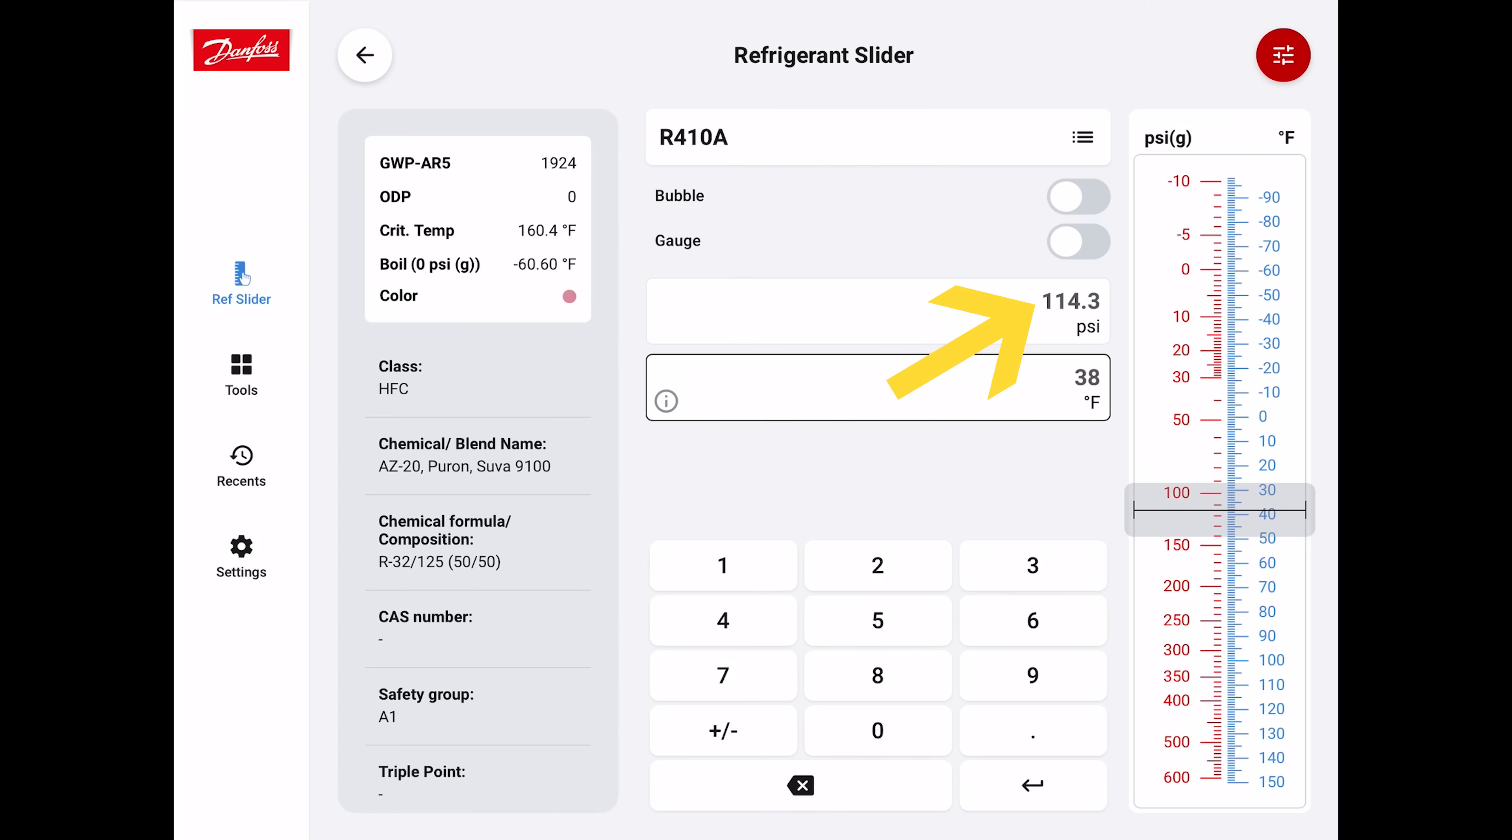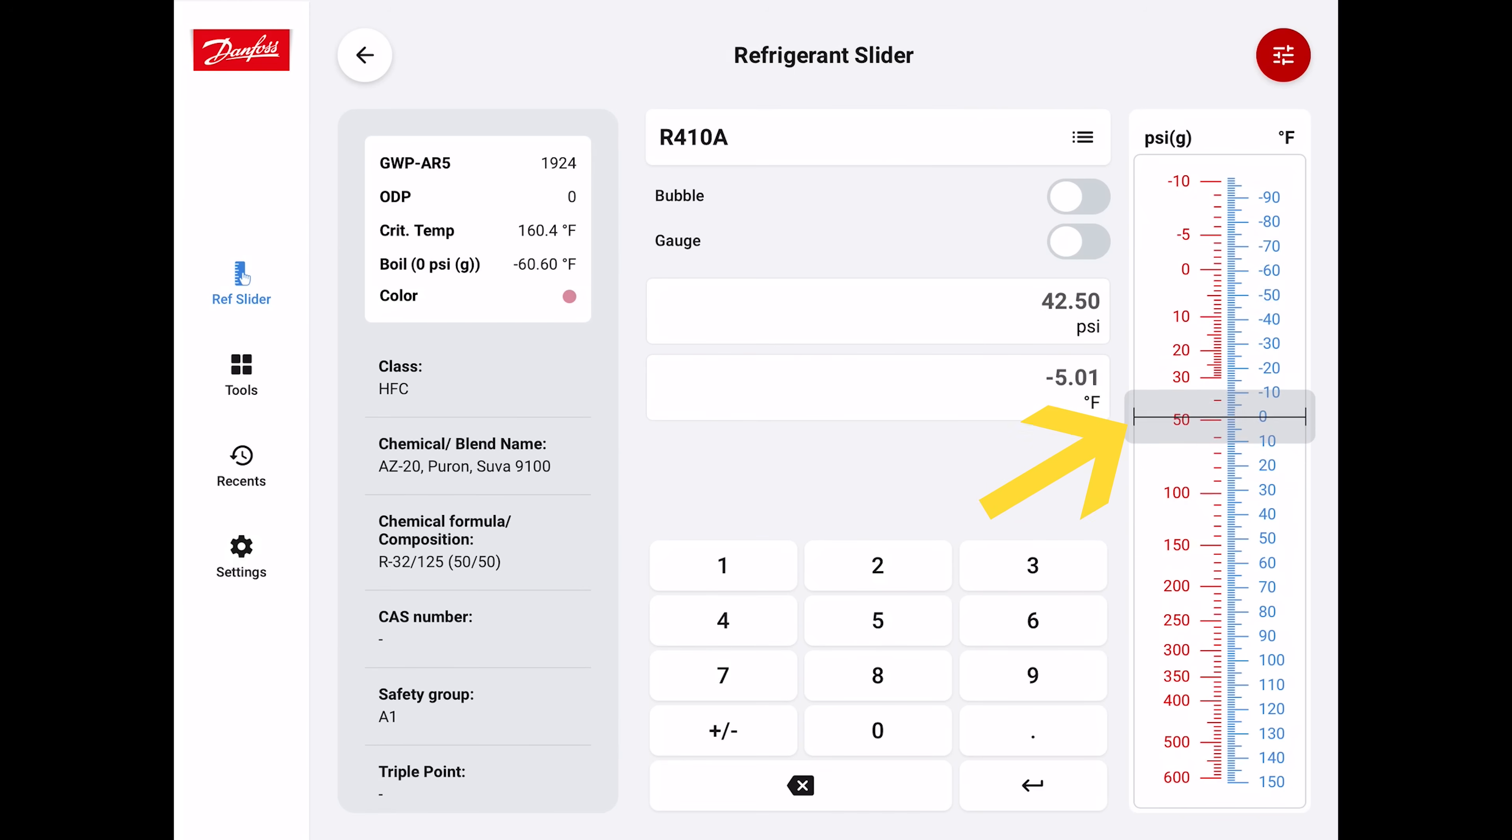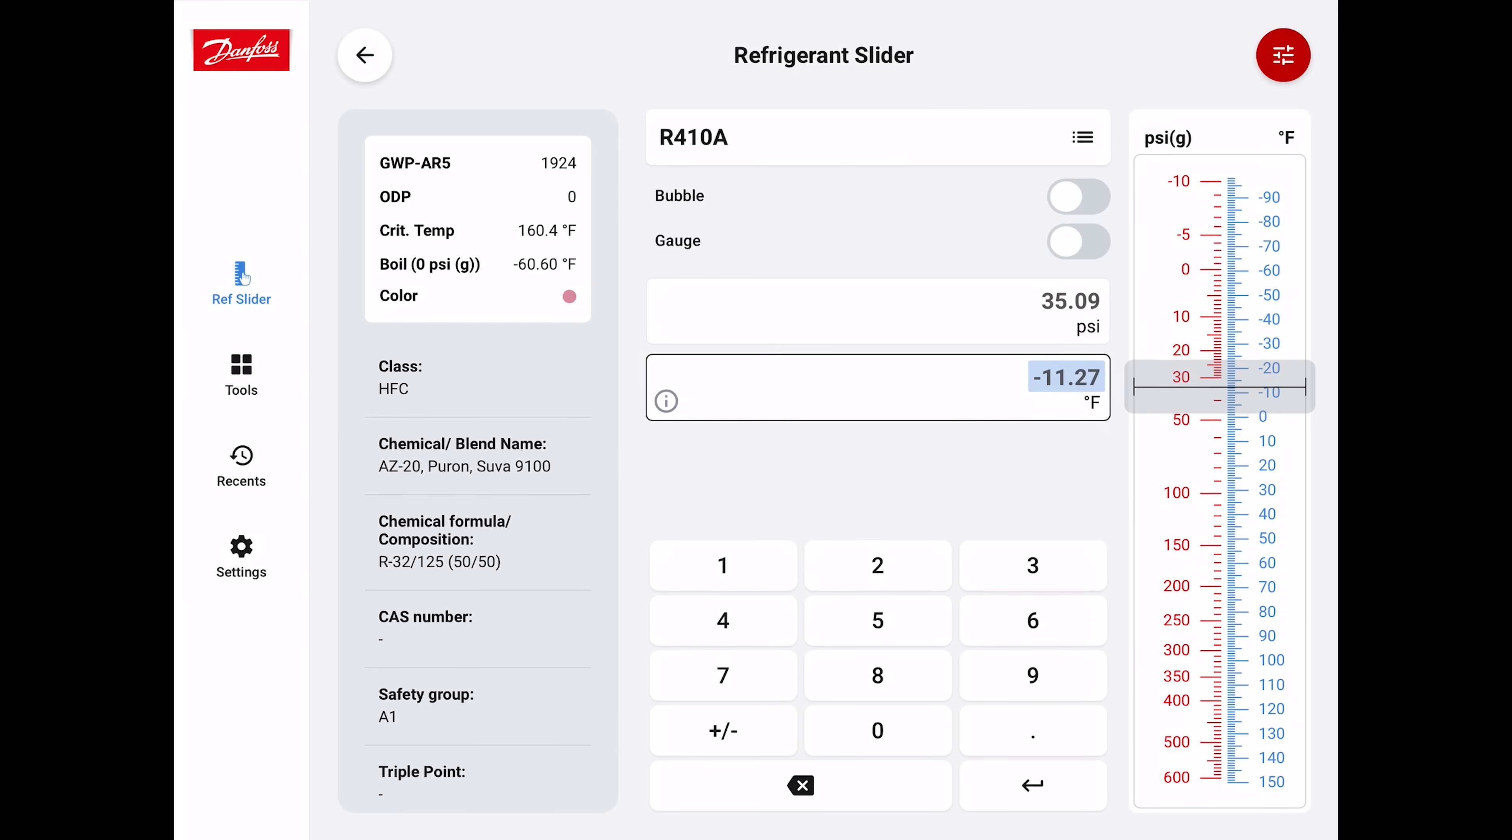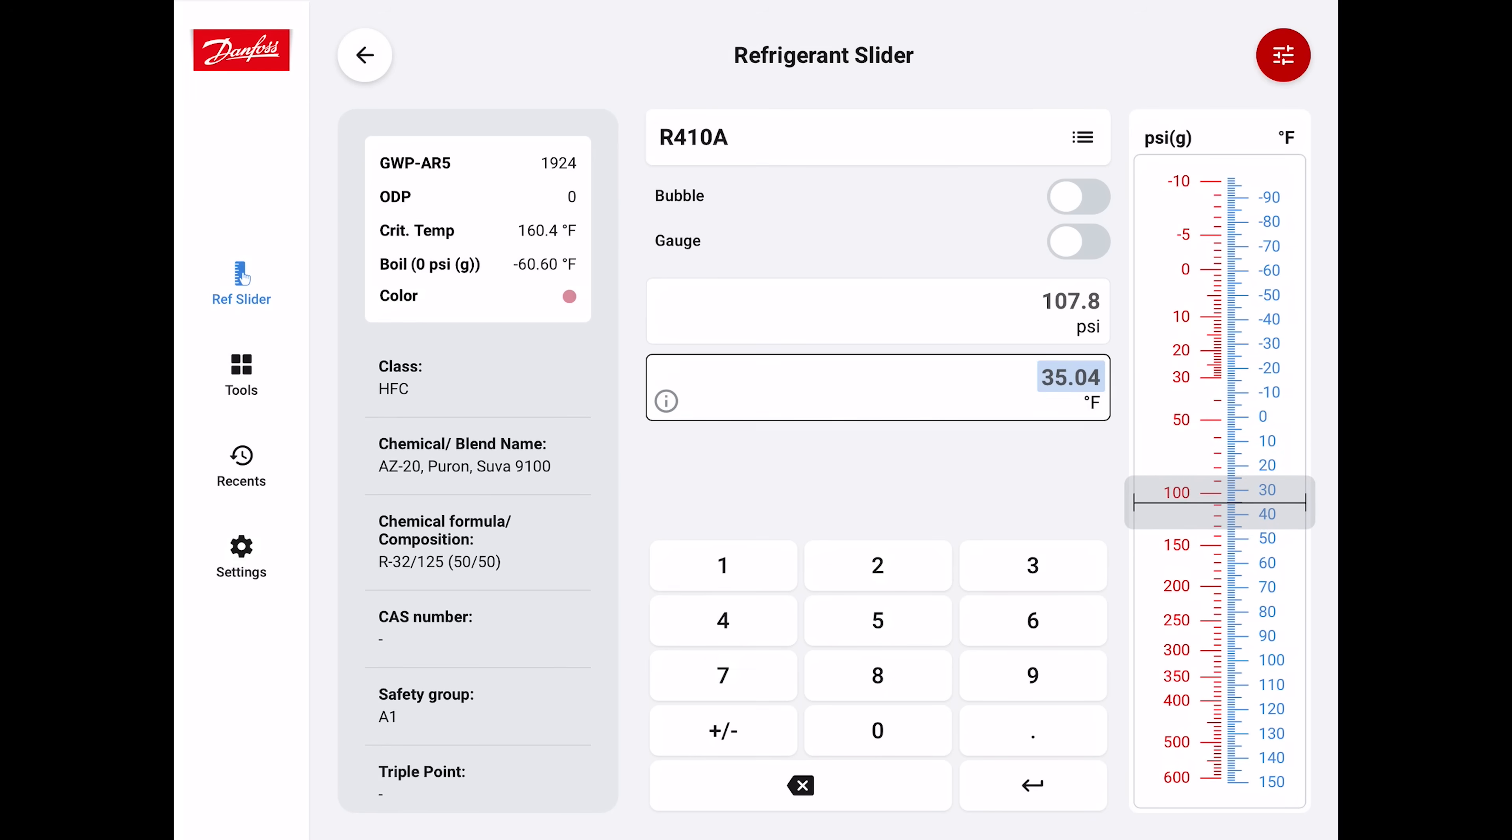That's the saturated temperature in the middle of the evaporator coil if you read the pressure on the vapor line of 114.3. Over here on the right-hand side, you see the slider. If your evaporator coil was 35 degrees, you see the temperature for the pressure is 108 PSIG, showing 107.8.